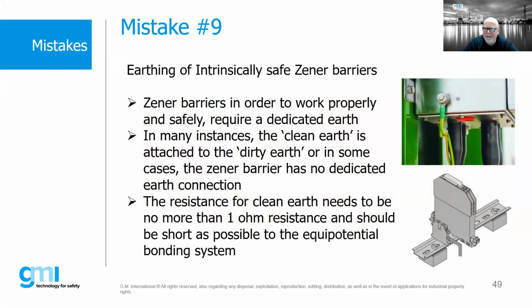Actually, I have one more: earthing of intrinsically safe Zener barriers. We need to make sure that if we're using Zener barriers, we're using a clean earth, separate from our normal dirty earth. This is one of the biggest issues we see — people take Zener barriers and fail to earth them to a dedicated IS earth. That earth needs to have less than 1 ohm resistance, and should be as short as possible to the actual physical ground.